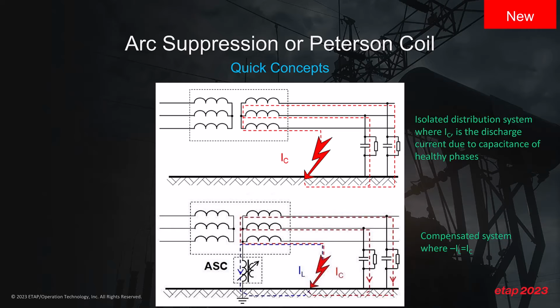So during an earth fault, the arcing grounds are self-extinguished by the coil, and also in the case of sustained faults up to a certain degree, depending upon the rating of the coil. And it's able to reduce the earth current to a low value so that the continuity of the supply to the healthy phases is not interrupted.